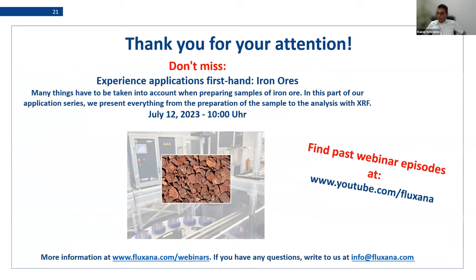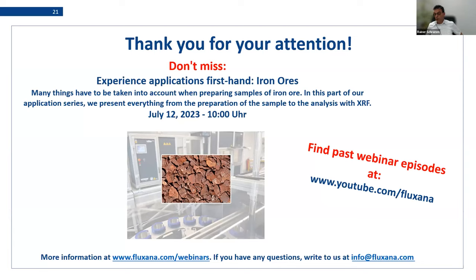If those were all the questions, I'd like to thank you for joining my webinar. If you have more questions or want better explanations, send me an email — I'm always willing to get into discussion. If you have ideas or suggestions for the next webinar, examples for practical use of correction models, I always appreciate it. One last question: if the XRF manufacturer did not install the correction in advance, could we use it? Yes, you can use it if the software offers it. If it's empirical you need standard materials to calculate the factors; if it's theoretical you just use it and validate with some standards to verify it works correctly. Thank you very much, see you in the next webinar, bye-bye.